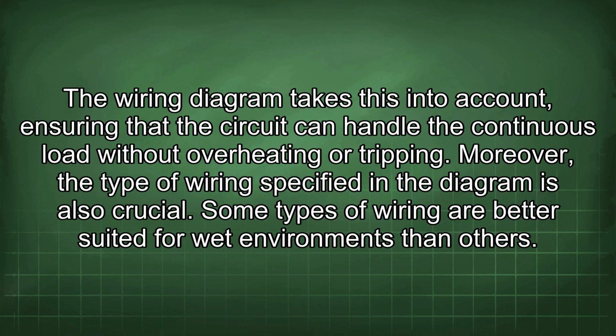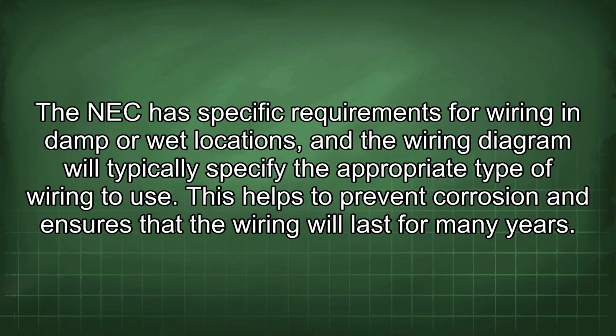Moreover, the type of wiring specified in the diagram is also crucial. Some types of wiring are better suited for wet environments than others. The NEC has specific requirements for wiring in damp or wet locations, and the wiring diagram will typically specify the appropriate type of wiring to use. This helps to prevent corrosion and ensures that the wiring will last for many years.